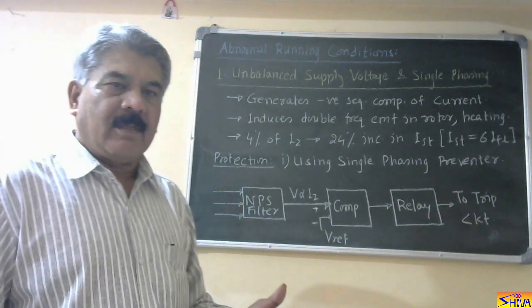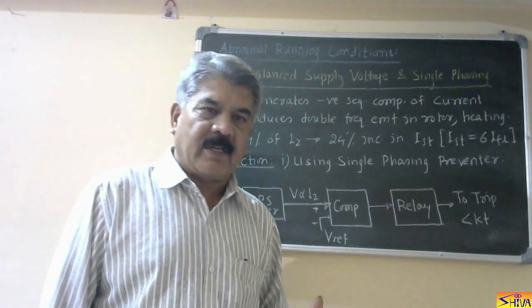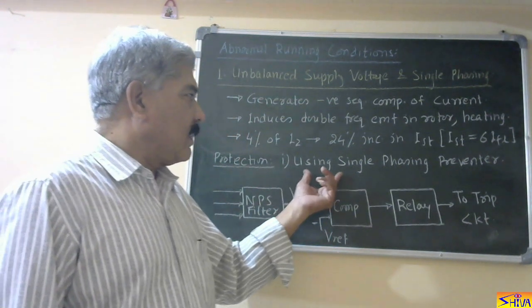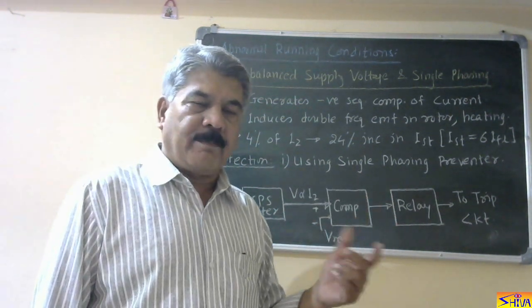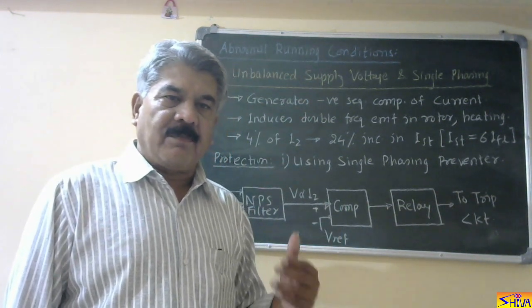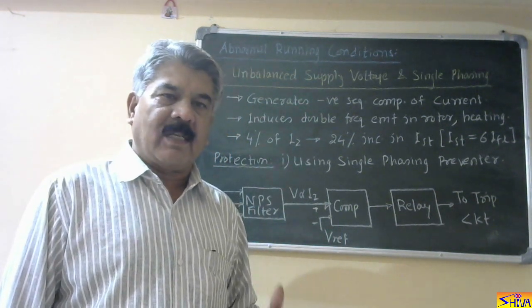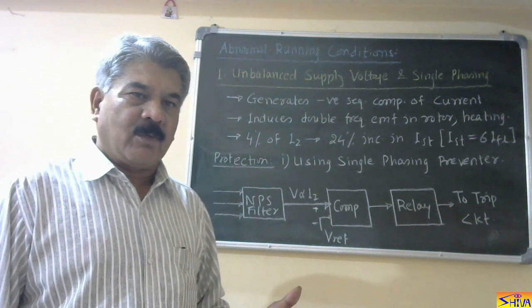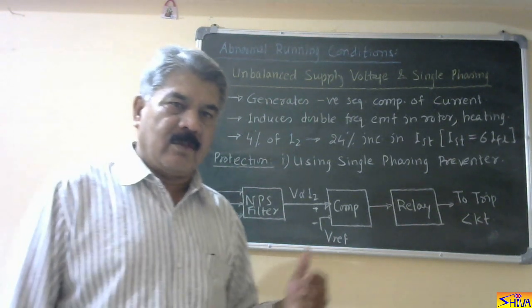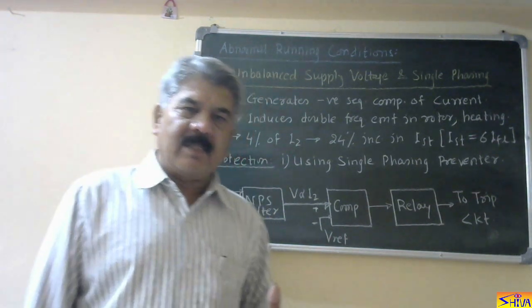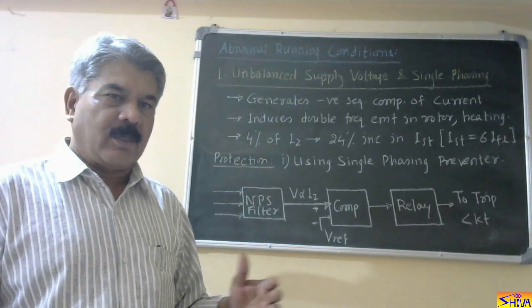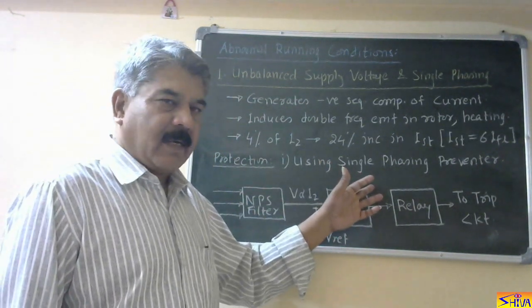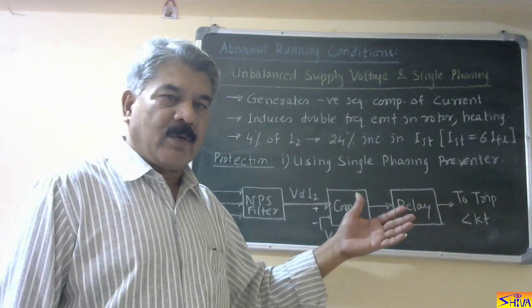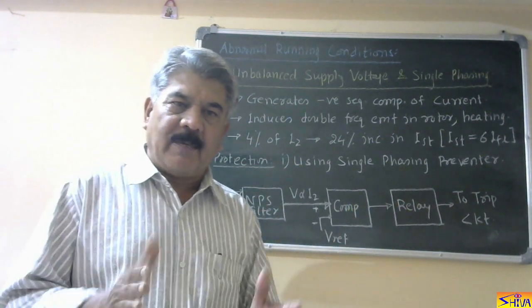The second protection is not a separate protection. Please remember, this single phasing preventer is used for big motors, large motors, as well as very large induction motors. It is not used for medium size and small induction motors. That comes under the second type of protection, which is not a separate protection.